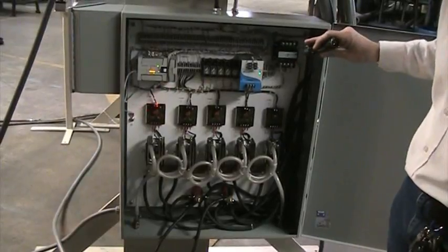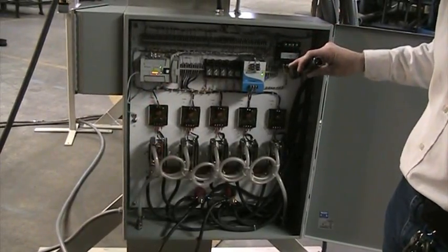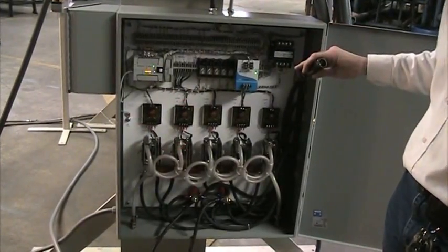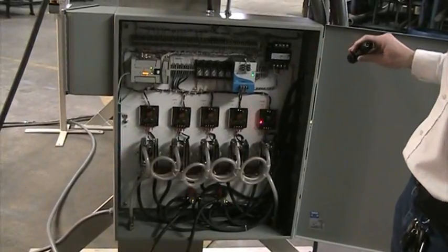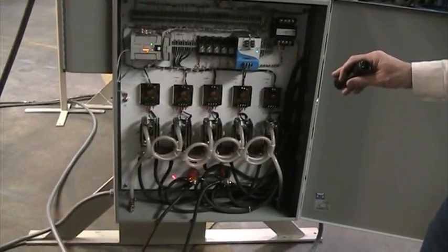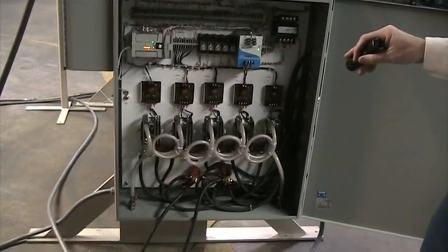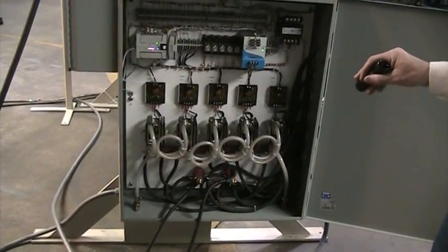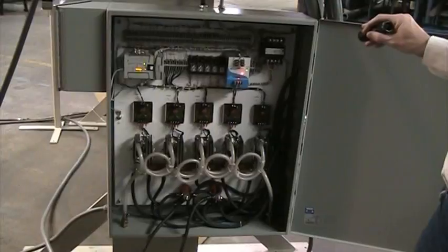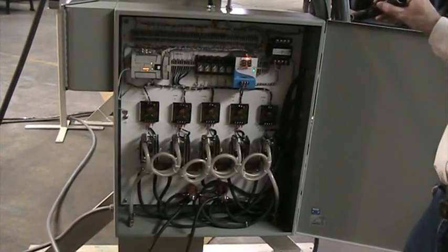Those are what turns on each of the individual SCRs. You'll notice above each one you're labeled PT401. This is SCR1, and that goes to transformer number 1. PT402 for SCR number 2, which goes to transformer 2 all the way across the board to number 5. Now you notice down here we've got L1 and L2 marked. This is where we've hooked in our power, but for your purposes you'll hook in power to the disconnect box and they come to this location. Since we didn't want to knock a hole that you may not need into your disconnect, we just ran it straight to this location. And then finally up here on the side you've got the step-down transformer that provides power to the 24 volt DC power supply, which in turn powers the valves, the HMI, and all the different relays.